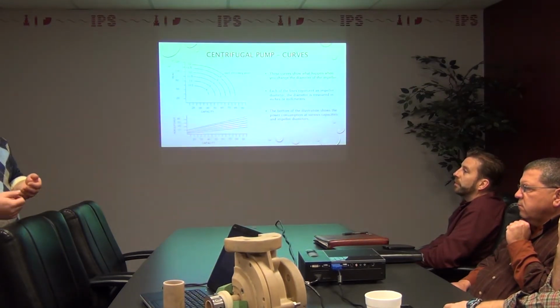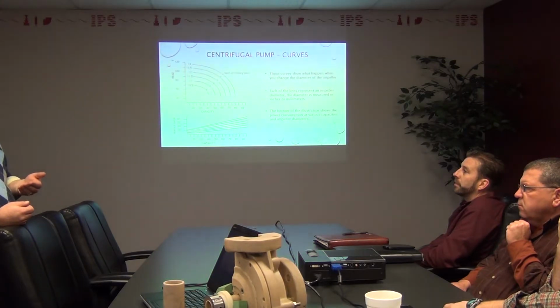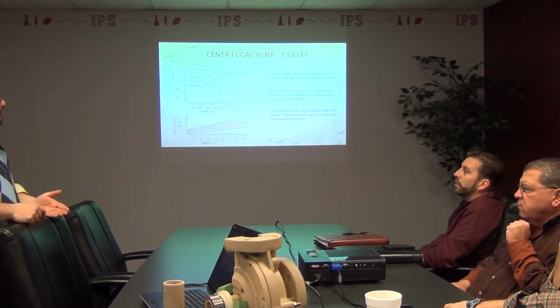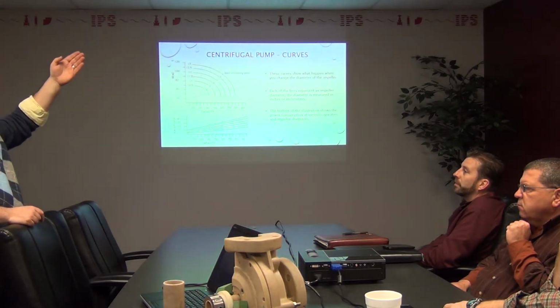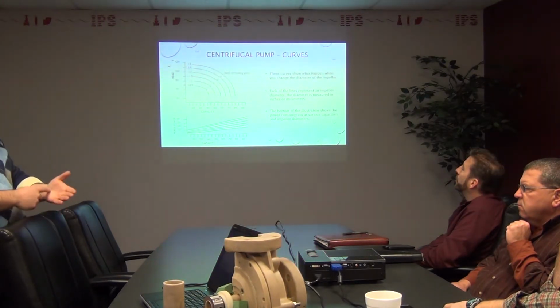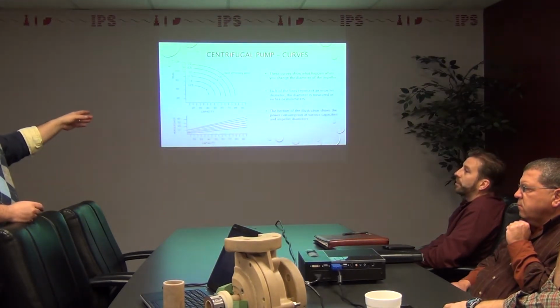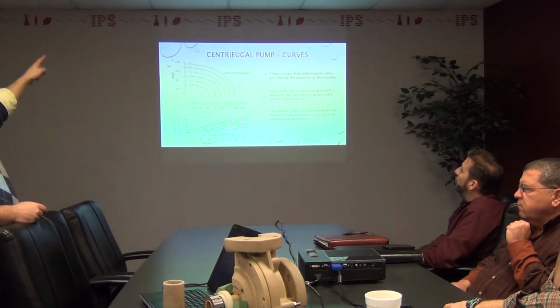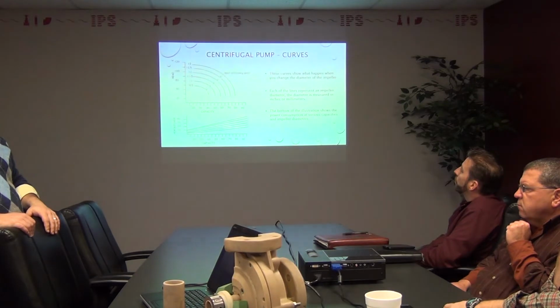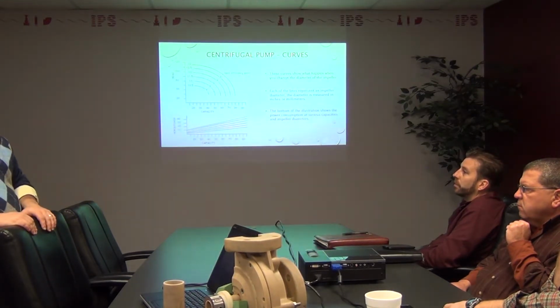And I pulled Dan aside and started yelling at him. I'm like, did you do this? Did you select this pump? Because it was 100-something feet, and the loop he was showing me was up 20 feet, over 5, and back down. I knew that was the scenario: we had a pump that was sized for way out here, so the motor was tripping out and failing. So I almost wrung his neck, and then I talked to the engineer.